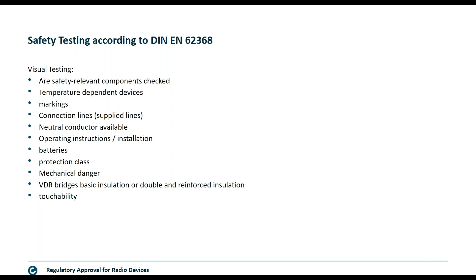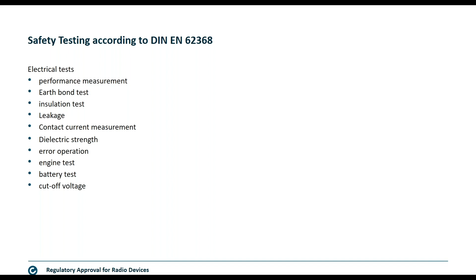I think these are quite self-explaining, so we could continue. We have visual testing: connection lines, neutral conductor available if it's net powered, operating instructions, whether there's a protection class, and so on and so on. We're doing some electrical tests like performance measurements, earth bond testing, isolation, leakage, dielectric strength, cutoff voltage, and battery testing. We're doing some mechanical tests. We have a test finger test. This is standard pressure brought to your device, for example, on the outer housing.